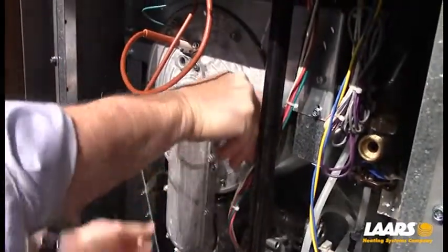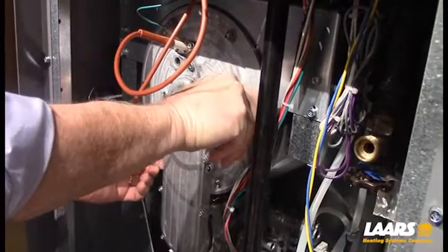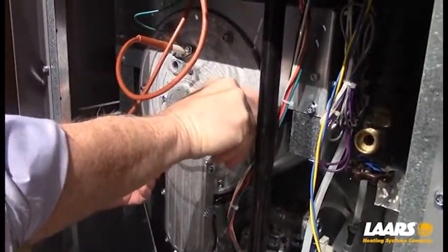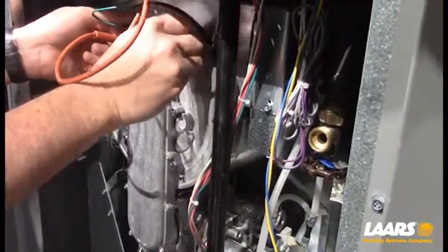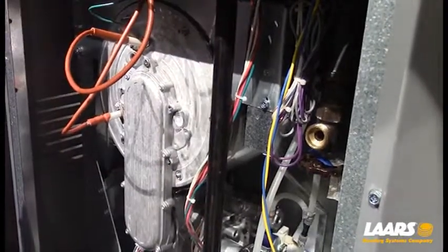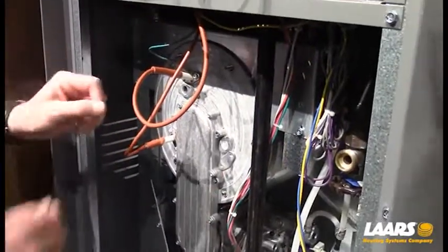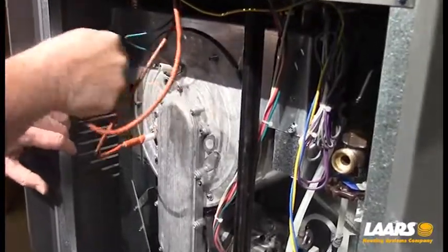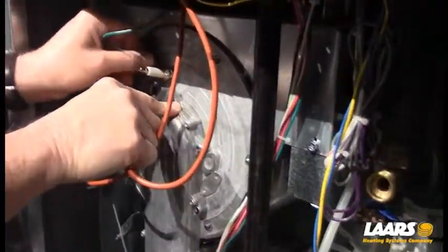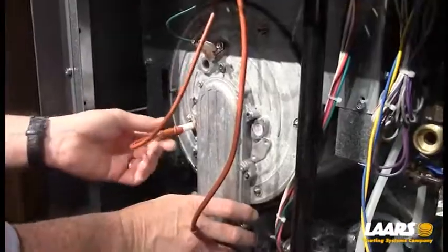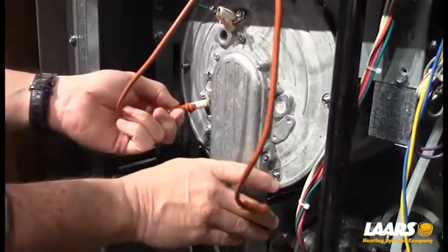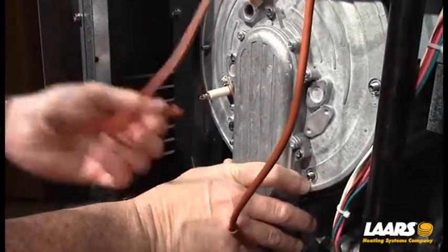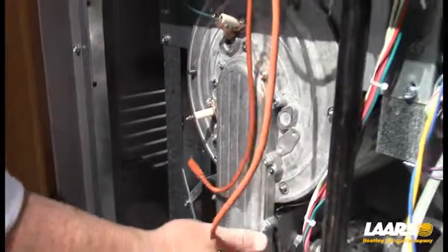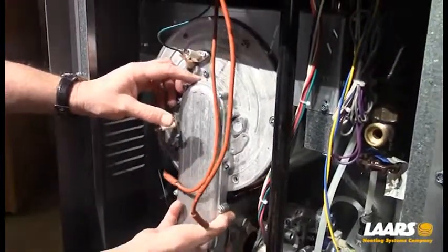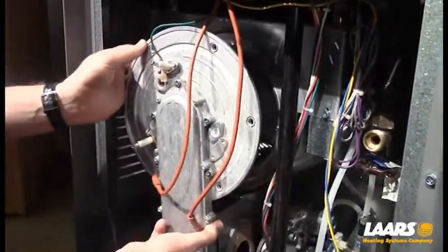Just going to rest these down on the bottom of the cabinet. Next, we're going to remove the ignition cable and ground wire from the igniter, as well as the flame rod wire from the flame rod. Now, the blower, arm, and burner plate are free. We can slide that forward.